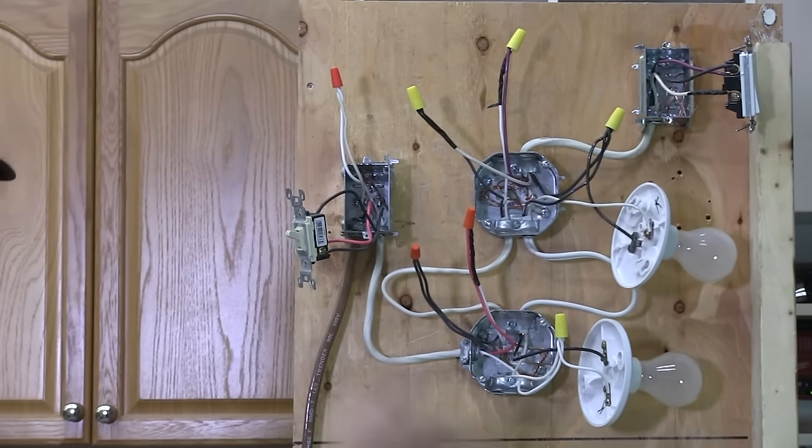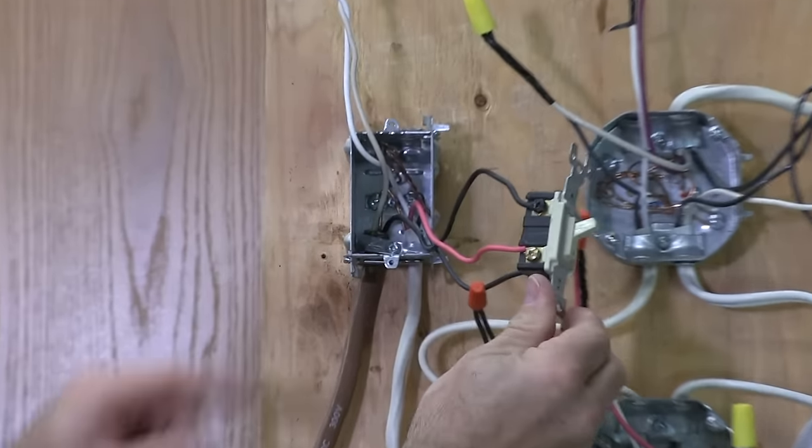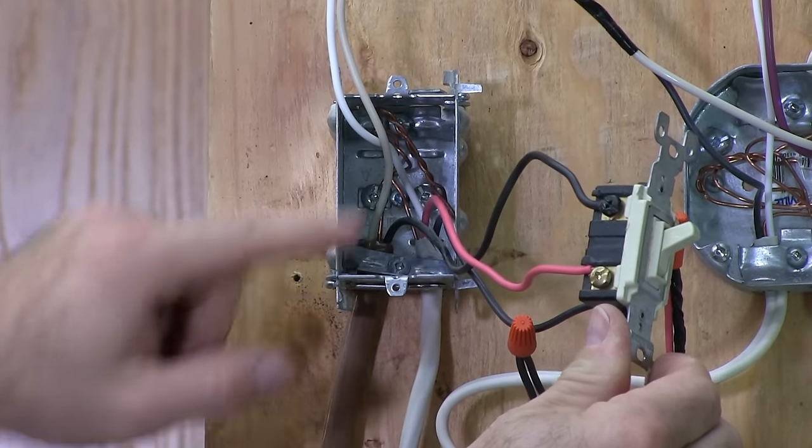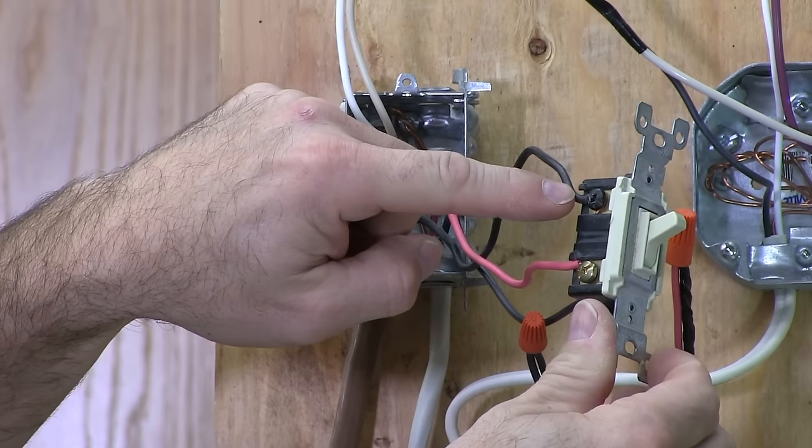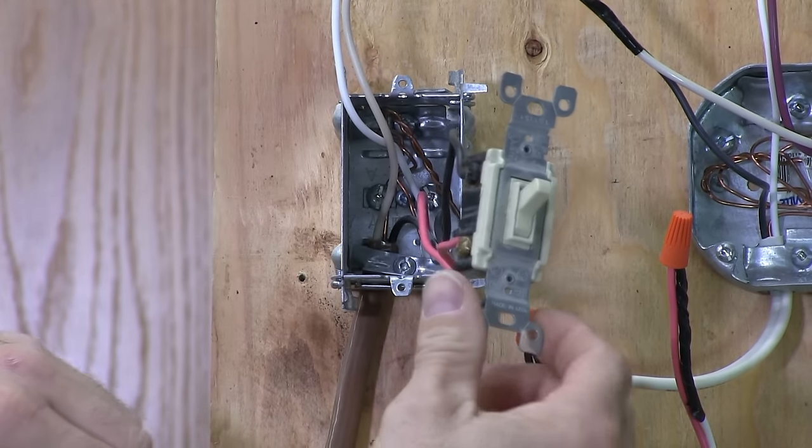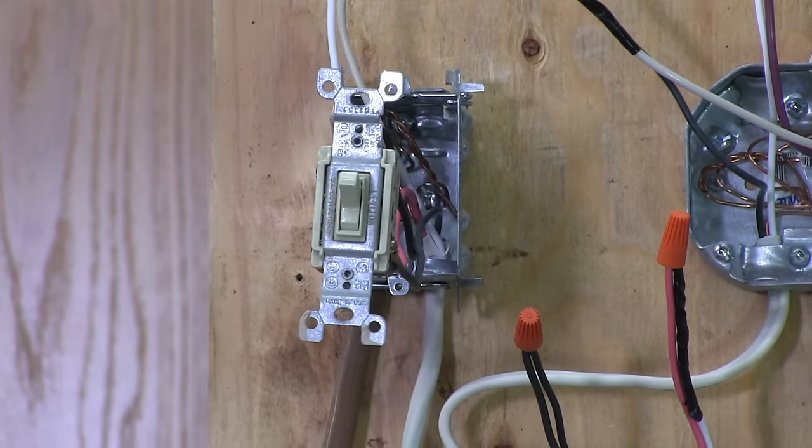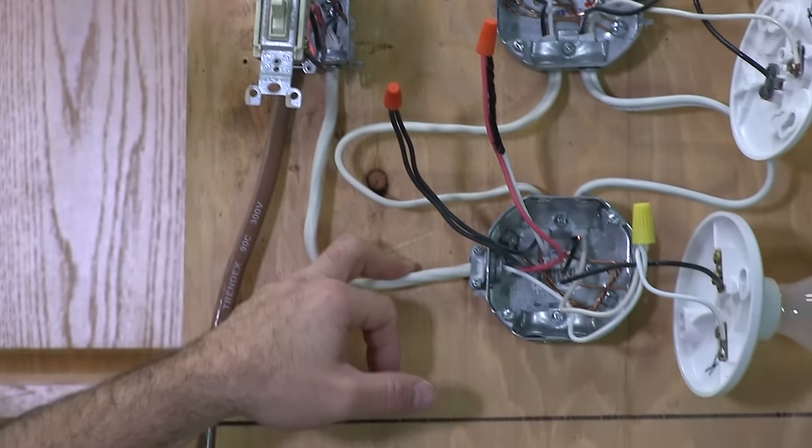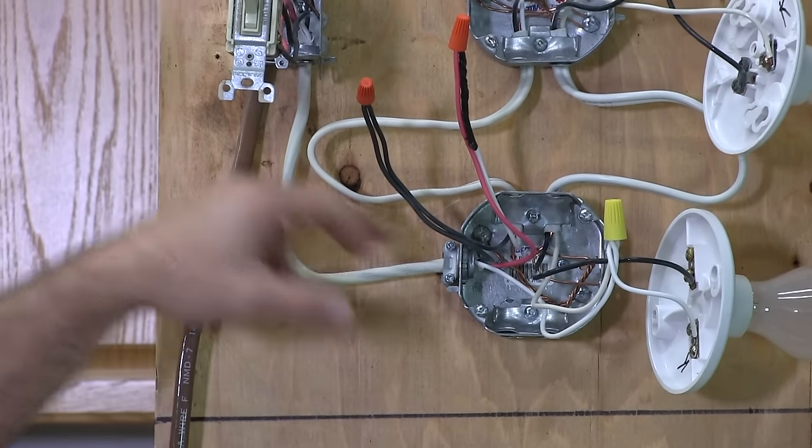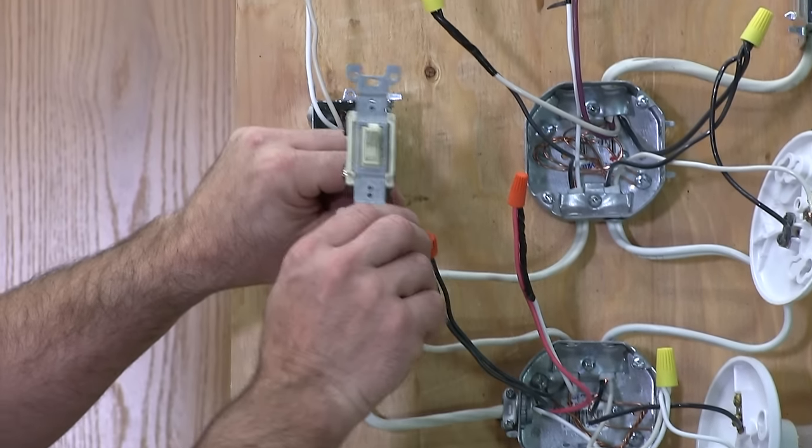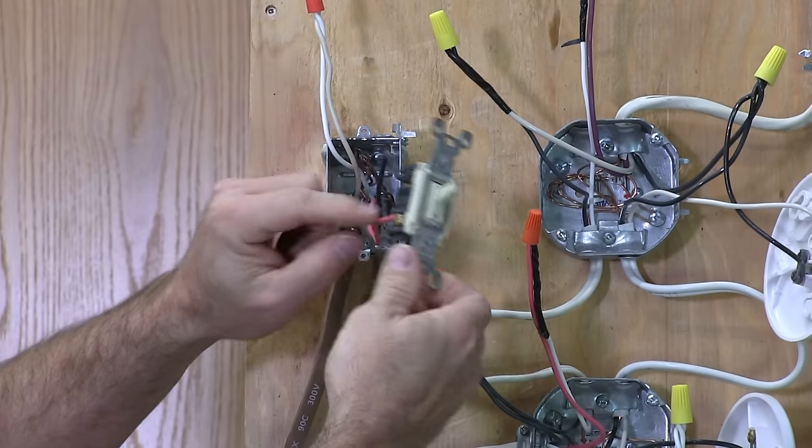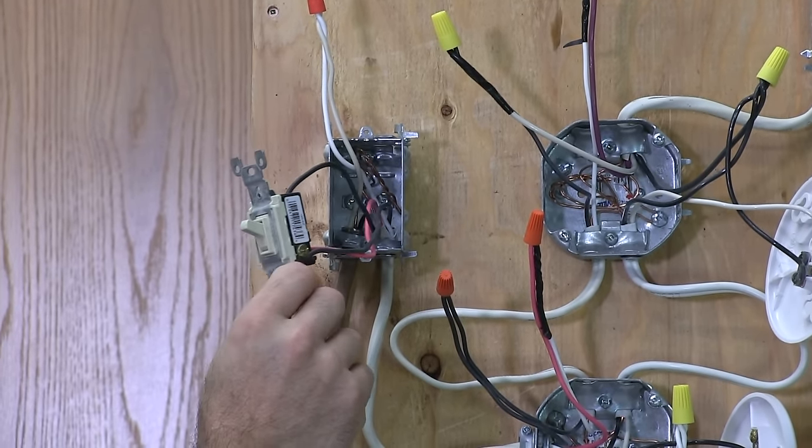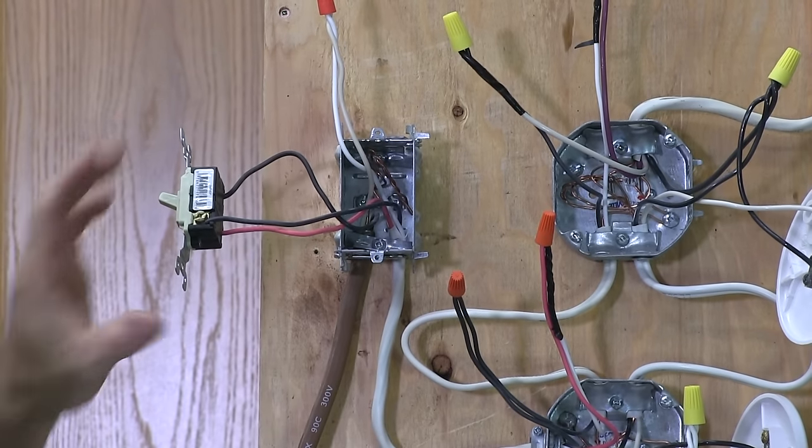Here we've got power coming into our first switch with a 14-2. Just like our other setup, we've got the hot wire, the black wire from the power supply going to the common screw, and this is a three-way switch. From this switch, going to the first light is going to be a 14-3. Up at this end, we've got a red and a black, and they're both hooked to the gold screws. So that looks after that switch.